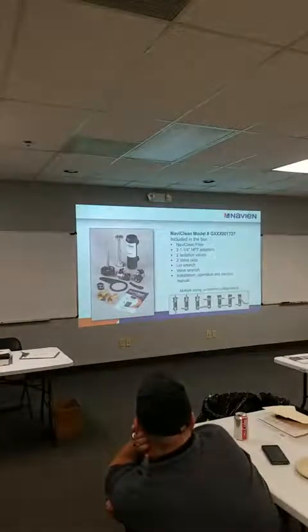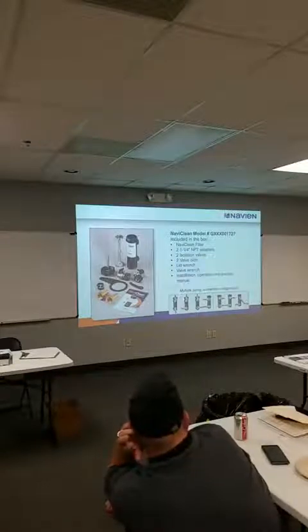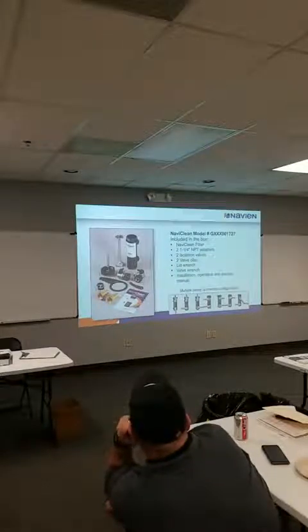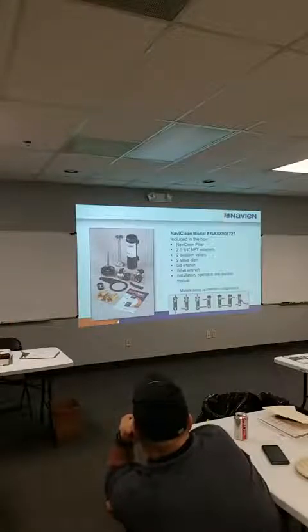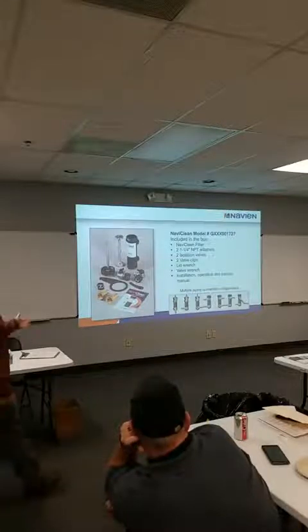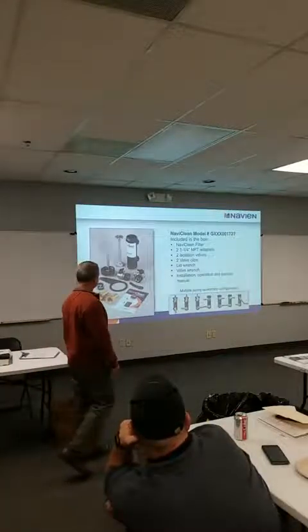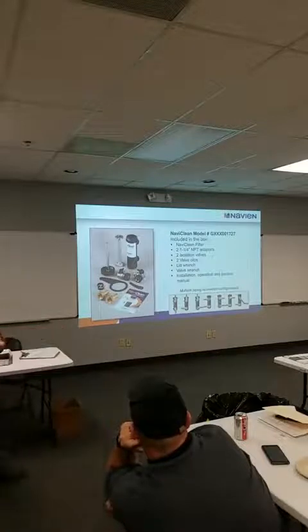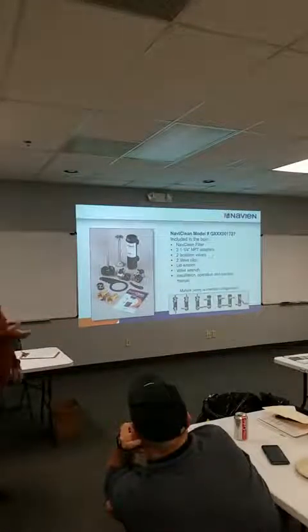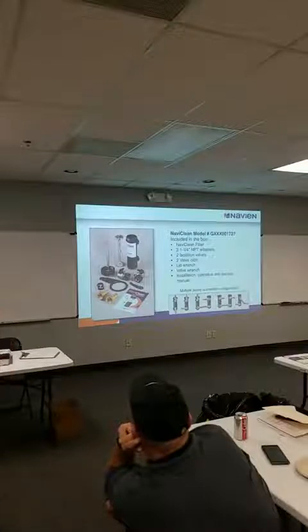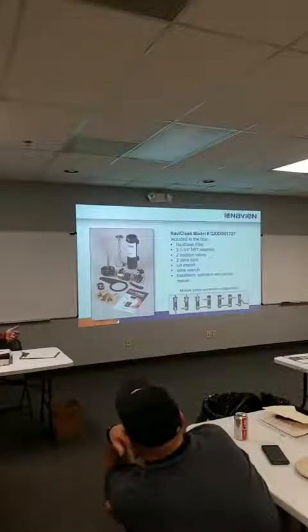So, we do sell this Navien. If you buy the fire tube combi, this comes in a box. I sell one from Fernox too. I sell one from Zomet too. I mean, it's a magnetic filter, magnetic dirt filter. You can isolate it, pull the magnet up, dump the filter, helps get all the magnetite out of the system if you're doing boilers. Any replacement boiler system that has mixed metal in it, I would put one of these things on. It's guaranteed to save the life of your pumps and your boilers. And I think you'd be blown away at the amount of stuff it traps.